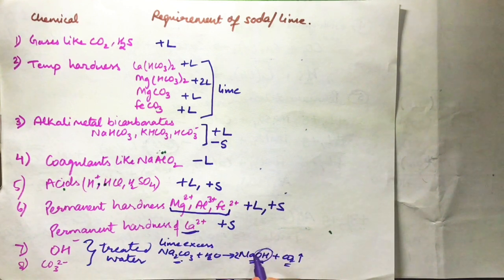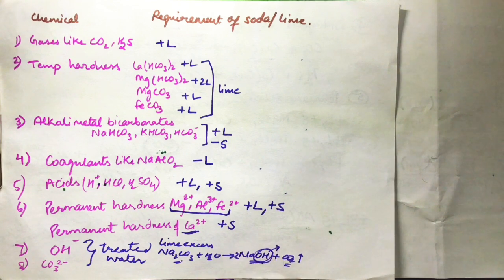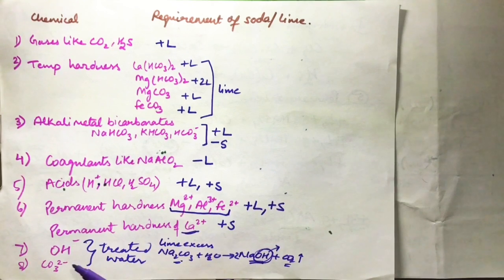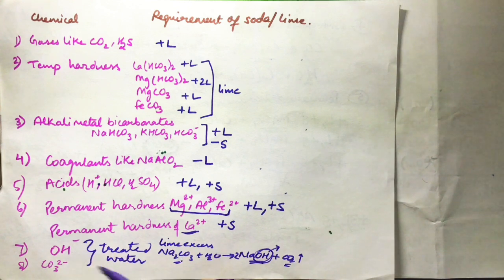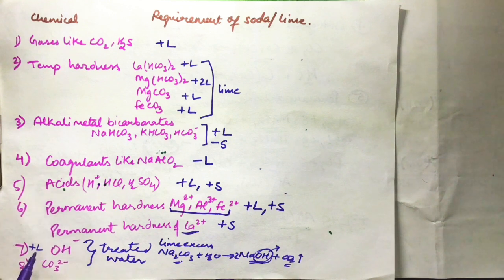This OH⁻ can be present in treated water from either lime or soda. So if treated water contains excess OH⁻, it can be attributed to both lime and soda. Therefore, in the case of OH⁻ excess, we have to add it in both lime and soda.